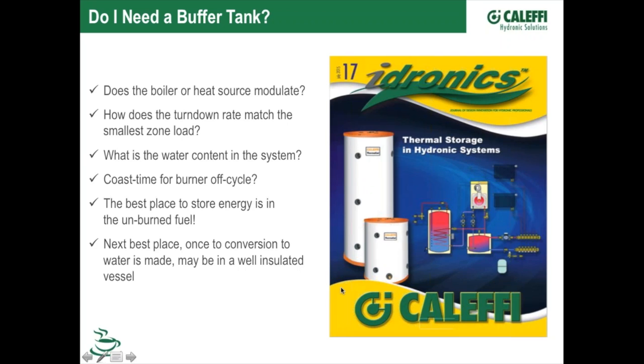It becomes a well-insulated vessel for storing heat energy in. It becomes an air separator because up here we have a dome top. As we go through this, we're going to drop the velocity in this big chamber. That's a great place for air to be removed out of it. The same thing happens at the bottom. We've got a dome section here with a drain valve there. So now that becomes a dirt separation device, an air separation device, a hydraulic separation device, and a storage vessel.